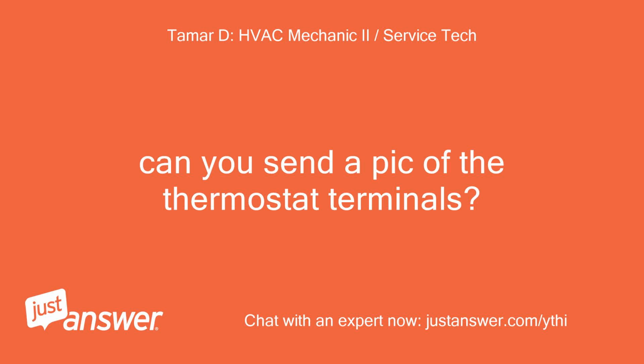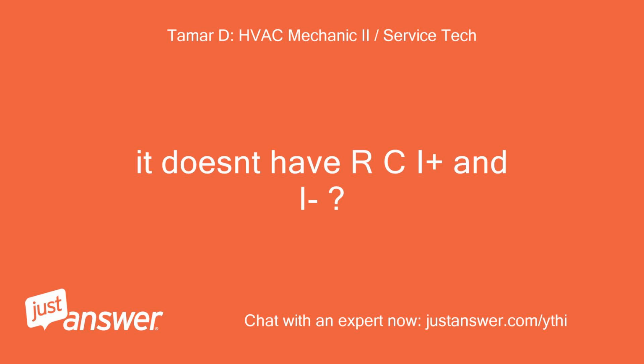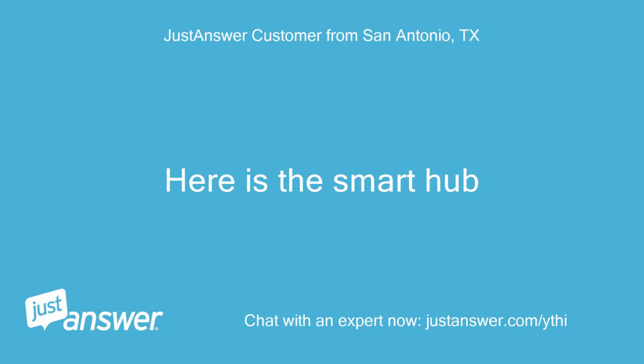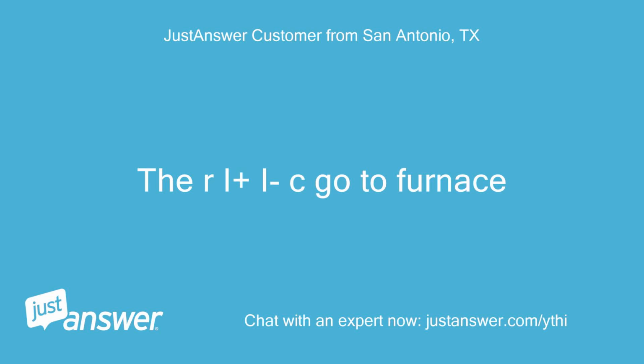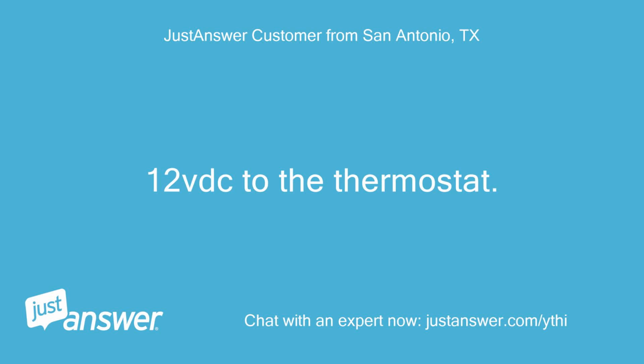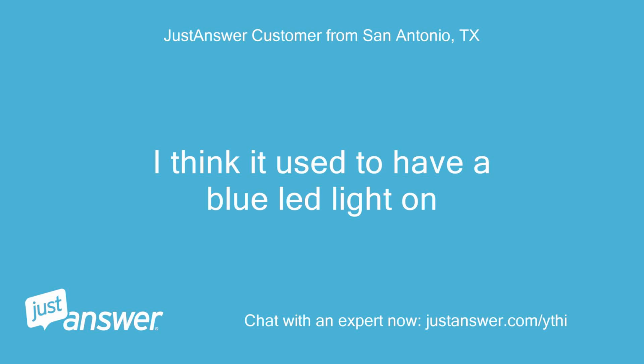Can you send a pic of the thermostat terminals? That has 26 VAC going to it but nothing coming out. It doesn't have R, C, I plus and I minus. Here is the smart hub. R, I plus, I minus, C go to the furnace. 12 VDC to the thermostat. But this unit isn't turning on. I think it used to have a blue LED light on.